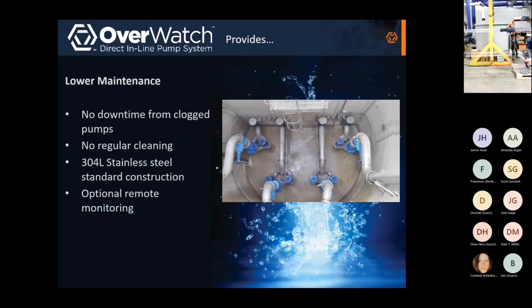So the OverWatch provides lower maintenance. There is no downtime for clogged pumps. You have 2 pumps on a common shared manifold—one pump is sized for 100% of the capacity, the other is there for redundancy. So while one pump is managing the flow, you have a backup there. If one goes into a clog phase, there's the other one to help out.